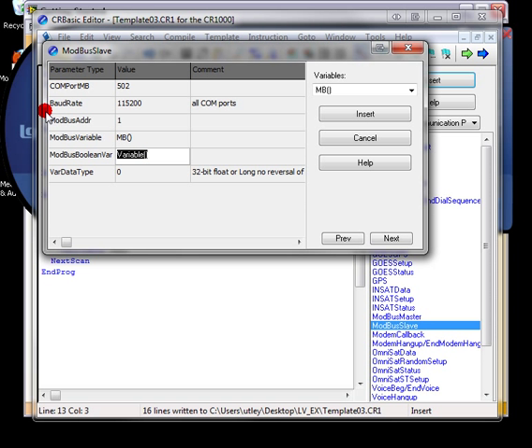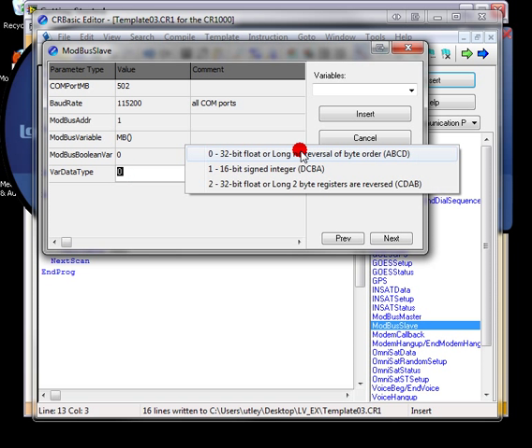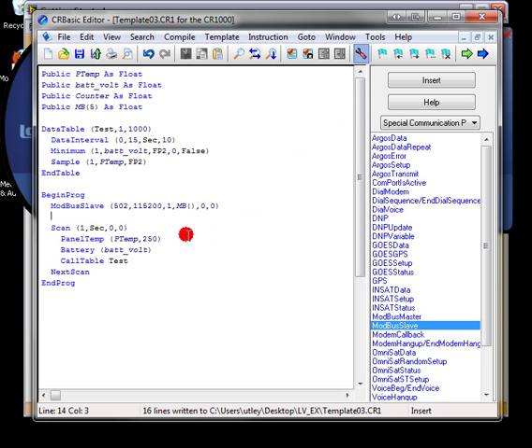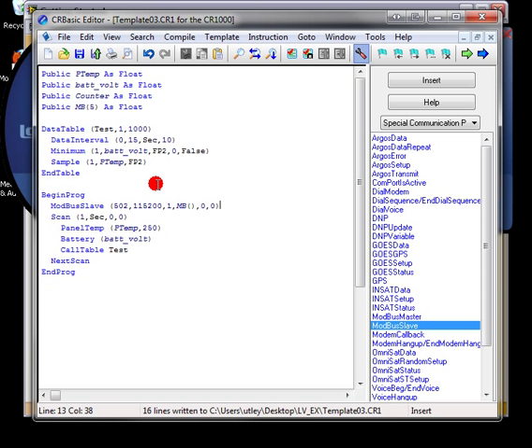Map it to our register array or holding register array there. And then I'm going to set this to zero because in this particular example I want to map the coils to control ports 1 through 8. And I'm going to select 32-bit float or long reversal of byte order. No reversal of byte order.